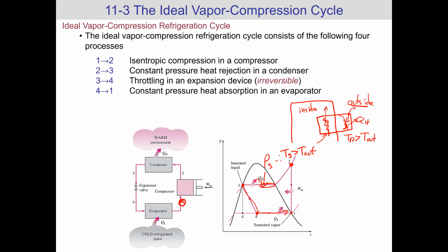So when it comes out of the evaporating coils, it's again a saturated vapor. And then again, the compressor pushes the pressure up in order to be able to reject the heat to the outside, right? As you compress it, the temperature also goes up, and then it goes through the condensing coils on the outside again, and the cycle starts all over. So what's great is that the refrigerant has saturation properties so that I can reject heat to the outside and absorb heat from the inside.